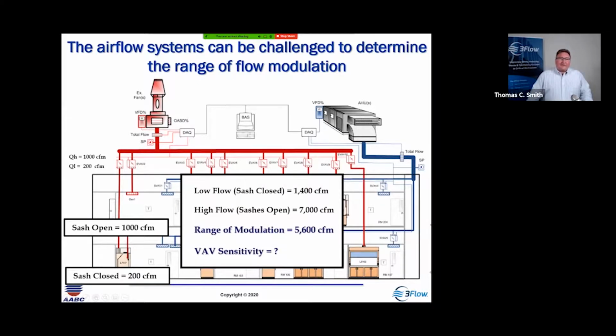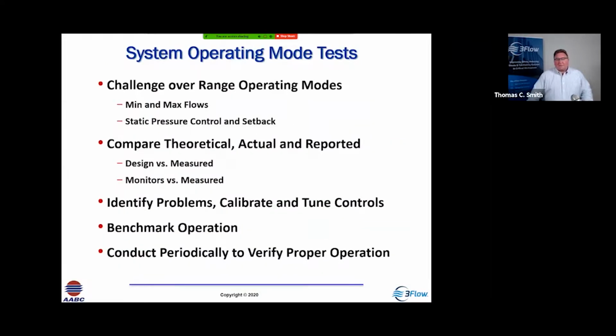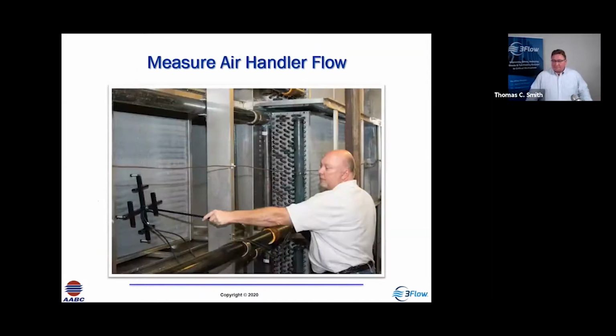If this is a 50,000 CFM air handler, how likely is it to see an 800 CFM flow change at a hood? How do we modulate the flow and make sure that we're tracking it properly and that we're tuning these loops to make sure that it is in fact as sensitive as possible, but not overly sensitive that it's starting to hunt and seek? So a system operating mode test is what challenges this over the operation.